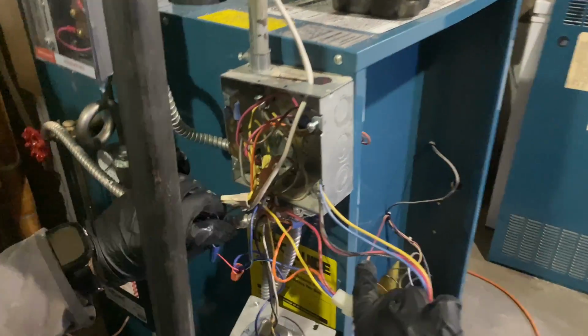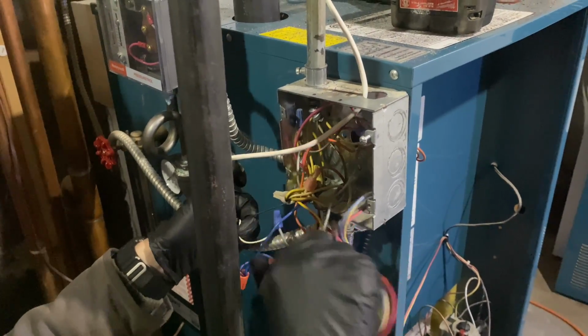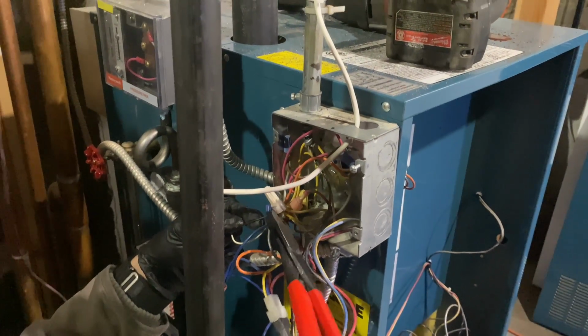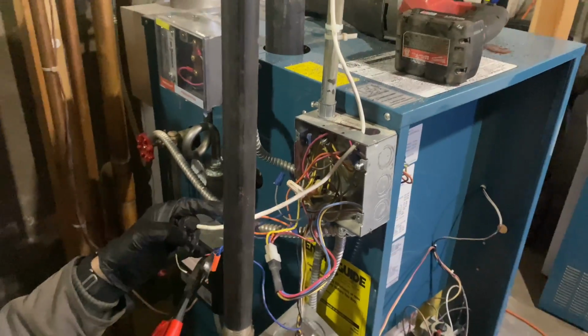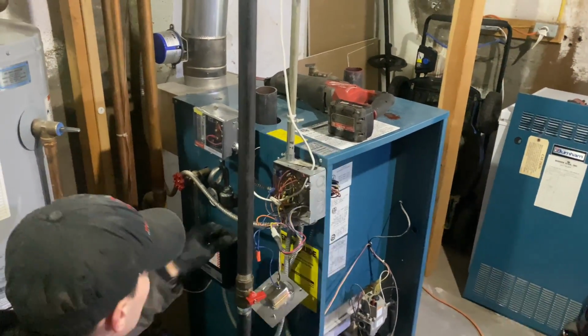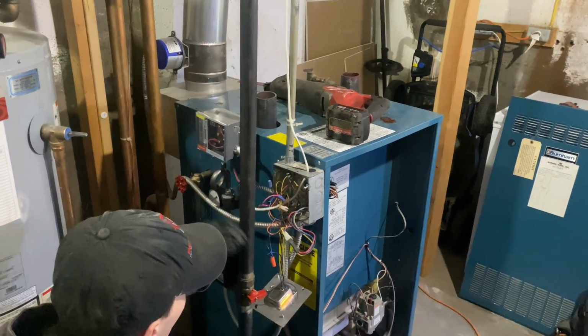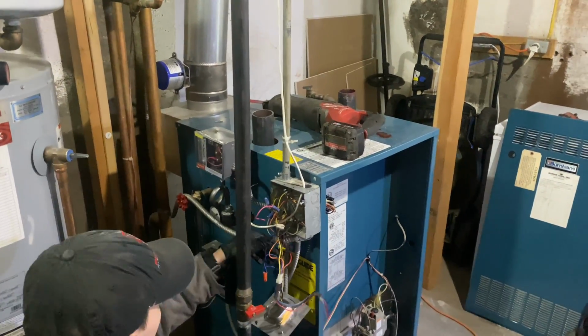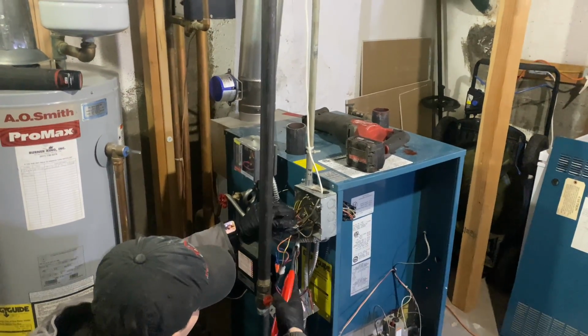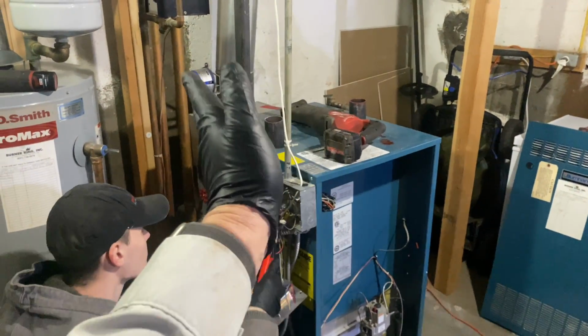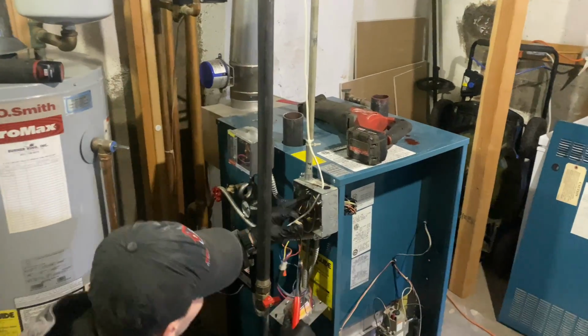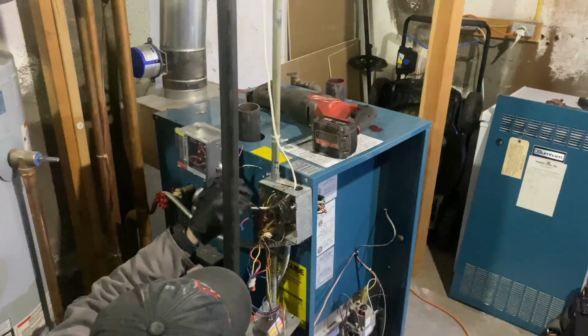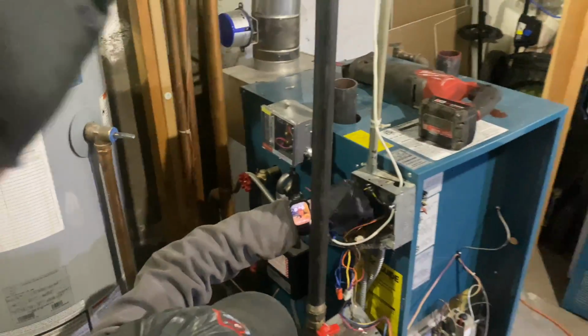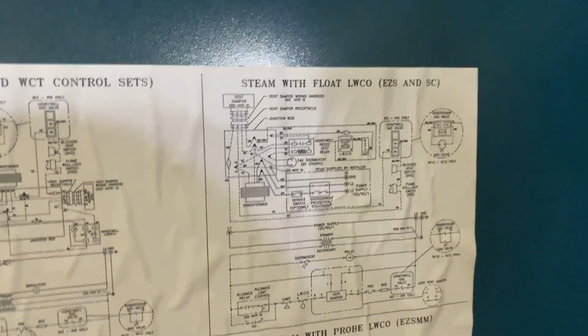Daniel is having the pleasure of working on the bird's nest equivalent of a menagerie of low voltage control wire. One of the best things I love about the SteamMax by U.S. Boiler, Burnham, is that everything is pre-wired. Everything. The only thing you have to wire in is a thermostat, an L1, neutral, and ground. Now, granted, we generally take off all the steam trim in order to get it into the home, the structure, for installation. But if you were intimidated by this in the past, your thermostat relay, your pressure control, all that good stuff, if you are unable to follow that wiring schematic right there, have no fear.